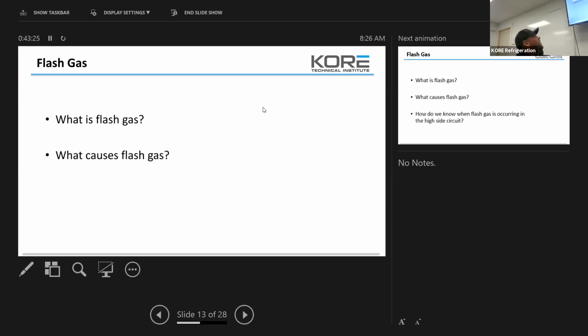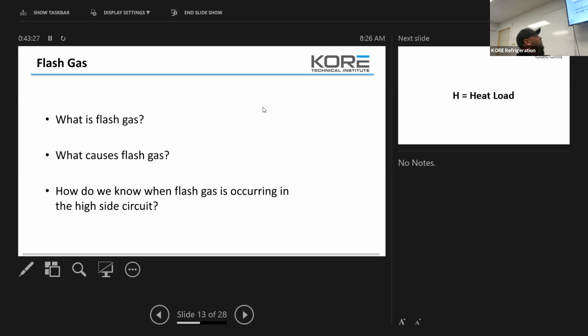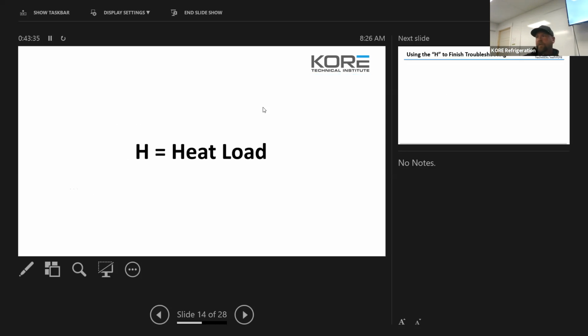So, what is flash gas? We just talked about this. What causes flash gas? How do we know when flash gas is occurring in the high side circuit? The easiest way to tell is to touch the liquid line. Flash gas is non-condensing. If for whatever reason you're not condensing through the condenser, it could be an overcharge situation. Somebody charged it in the middle of summer, put too much gas in it, so it started to throttle back and it's too impacted with gas. It could be plugged up. Could be a fan motor slowing down.